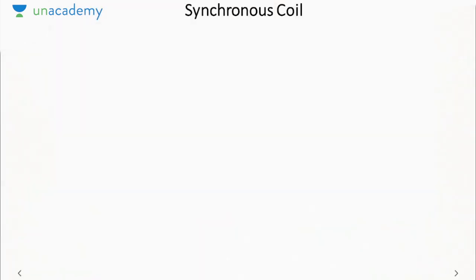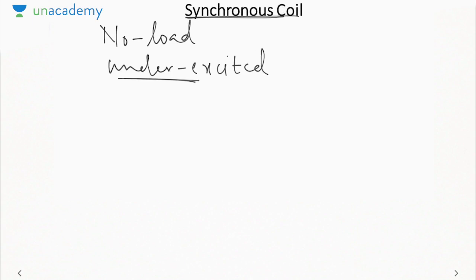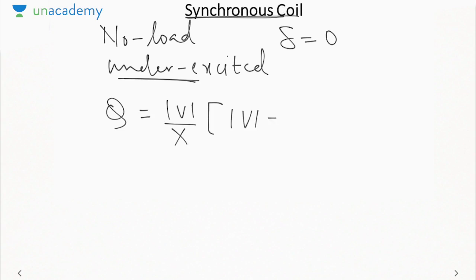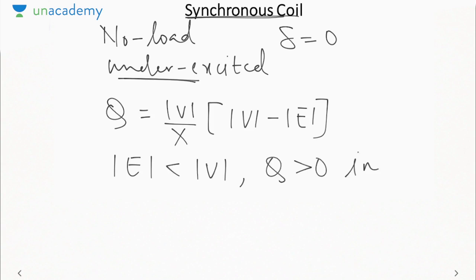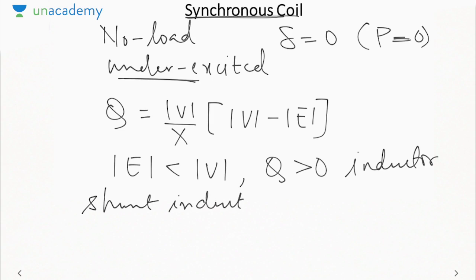Let us move to another device that is called a synchronous coil. It is the analog of an inductor. So it is the synchronous motor under no load condition running at underexcited condition. So here we have no load and underexcited. If no load is there, that means delta is 0. So reactive power is mod V by X times (mod V minus mod E). So mod E is less than mod V, Q is greater than 0, it acts as an inductor. And an inductor does not have any real power, so here also P is 0. That is why it shows a purely inductive behavior, that is called a synchronous coil. So it will work as a shunt inductor, and a shunt inductor was used to control over voltages, or it was used in case of leading power factor load.